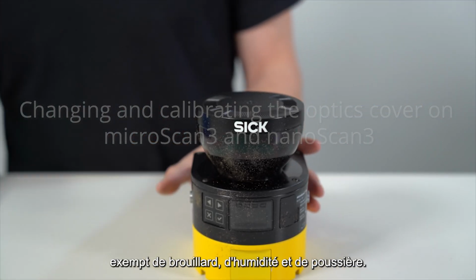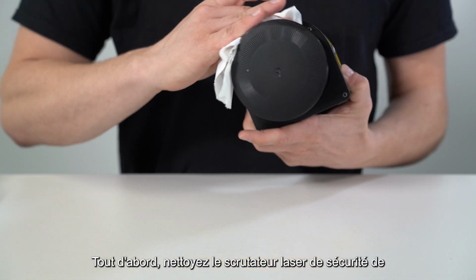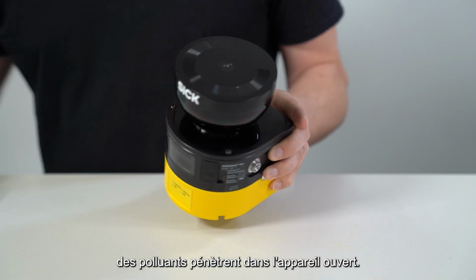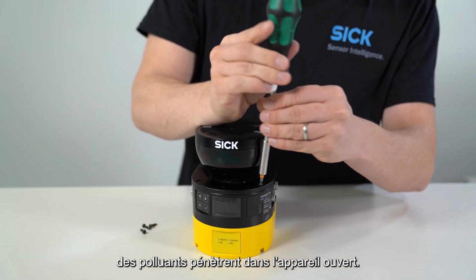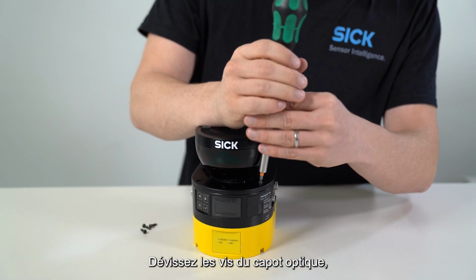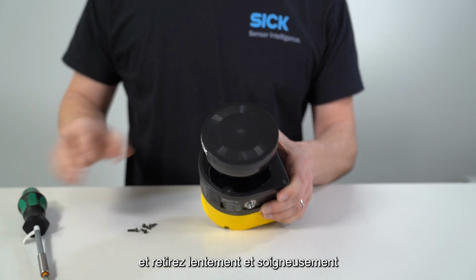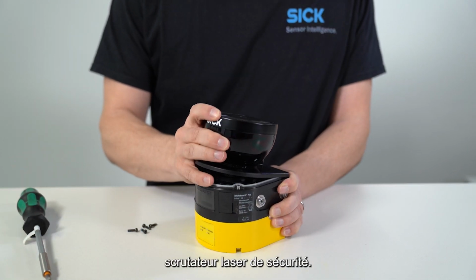To change and calibrate the optics cover of microScan3 and nanoScan3 safety laser scanners, make sure that the environment is clean and clear of fog, moisture, and dust. First, clean the safety laser scanner from the outside to avoid contaminants entering the open device. Unscrew the screws for the optics cover and slowly and carefully remove the optics cover from the safety laser scanner.